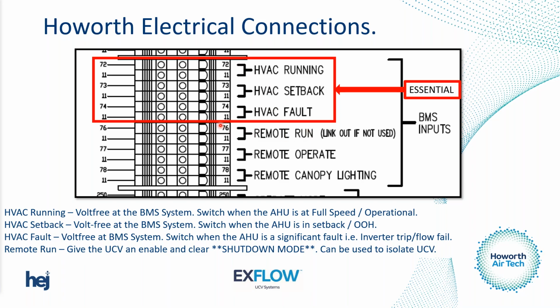But what we can do is we can take that signal and we can link it into what we call remote run. If we don't have remote run in, basically what happens is our PLC loses a run signal to all VFDs if we're using variable frequency drives, or we kill the control signal that goes to our electronically commutated fans in our bigger canopy. And what that enables is a complete shut off of the air handling unit and the UCV together, while we just monitor the ambient temperature. And then when we come in the morning, the HVAC will come on its own, and then the clinical teams will have to go to the theatre control panel and press operate, and the canopy will run up to full speed. So they're the things that are important and need to be noted.